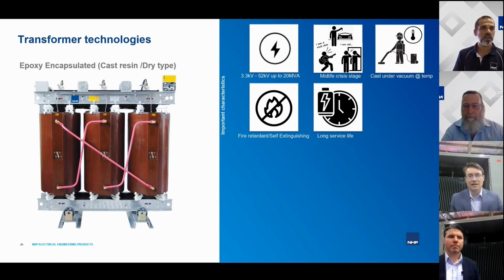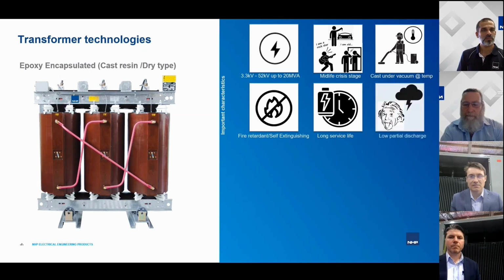So design life of cast resin transformers obviously depends a lot on the application. You have to make sure that the transformer operates within the resin temperature limits, and all this is done through design as well as protection devices. But there's another important consideration for service life, which is the quality of the resin itself. And the best way to check or detect the quality of the resin in practice is partial discharge testing, which is a standard routine test for cast resin transformers.